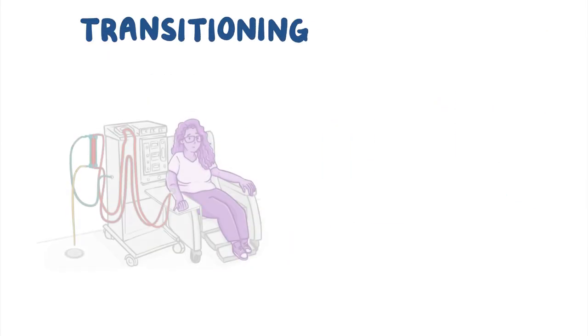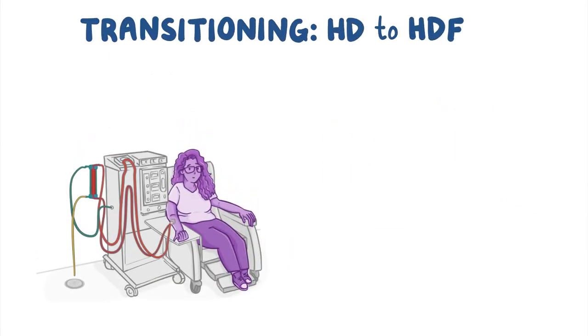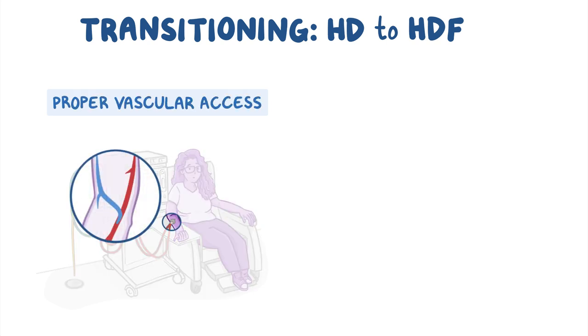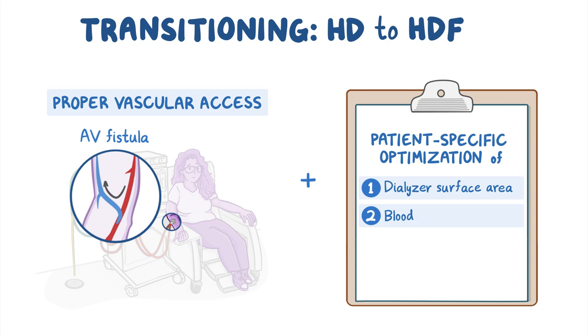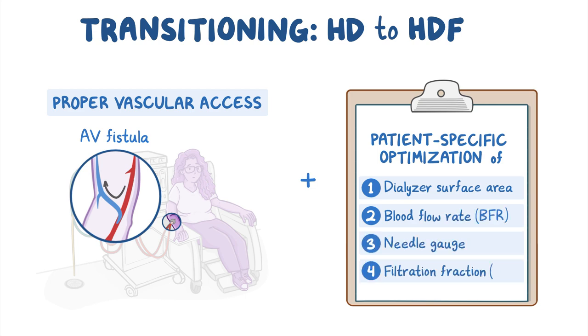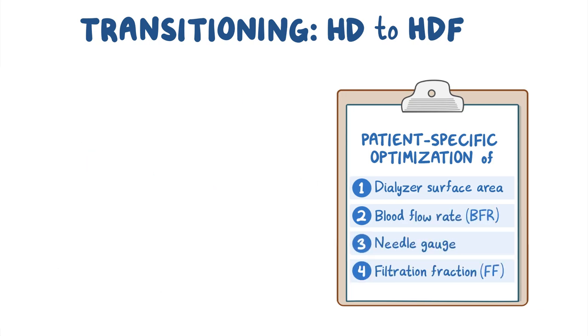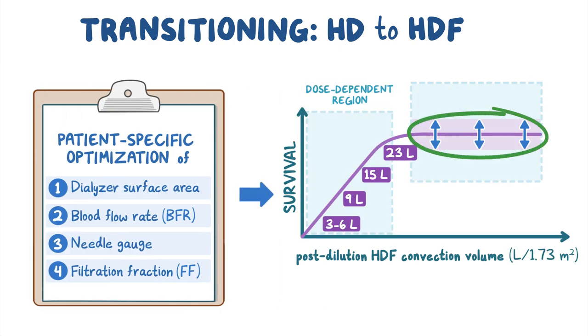Transitioning a patient from HD to HDF requires a properly functioning vascular access, preferably an arteriovenous fistula, and patient-specific stepwise optimization of the dialyzer surface area, blood flow rate or BFR, needle gauge, and filtration fraction or FF to achieve high convection volumes.